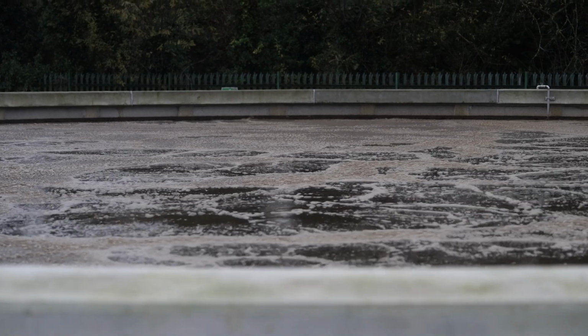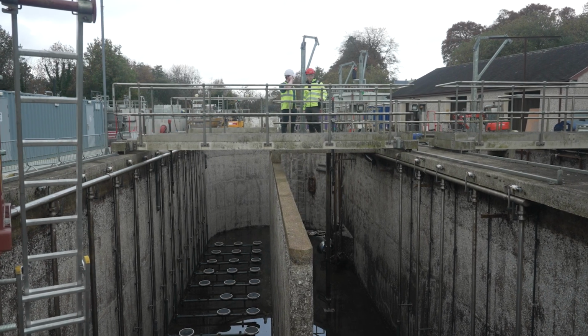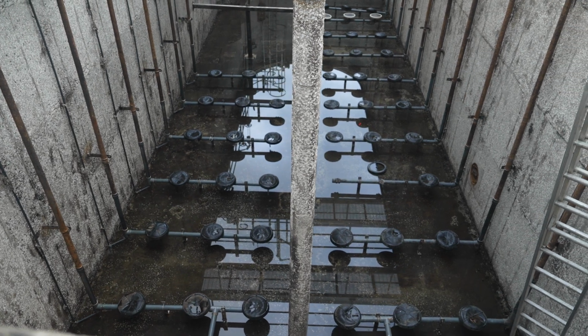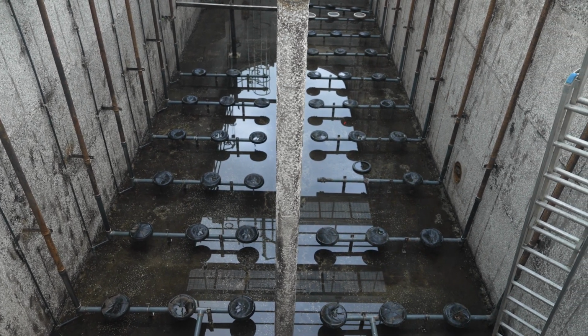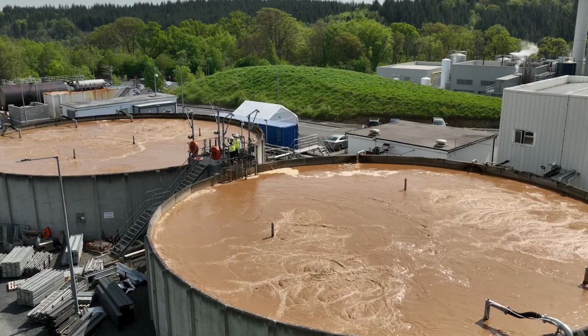Or you're going to use what may be considered best in class, fine bubble diffused aeration. But those diffusers are at the bottom of a tank, usually 5 or 6 meters underwater. Not so easy to get access to, not so easy to maintain if you need to maintain. With diffused aeration grids, when there's maintenance required, the problem is that you need to drain down or you need to lift them out in order to maintain them. The problem being that you can't supply aeration into the tank during these times.